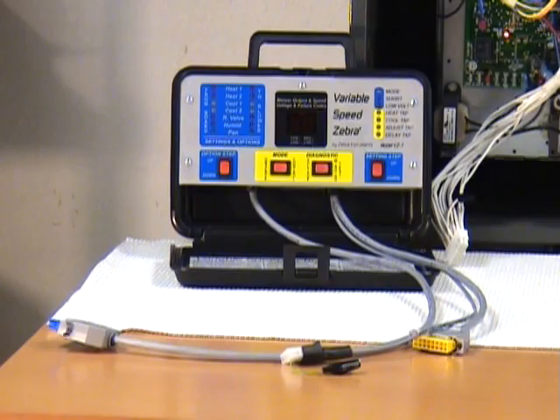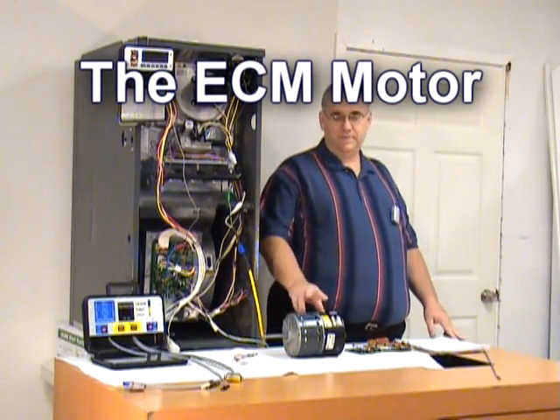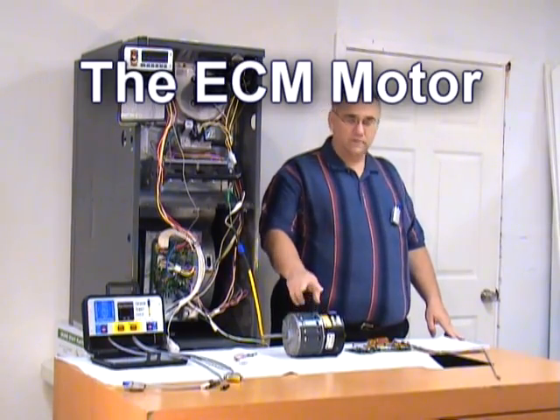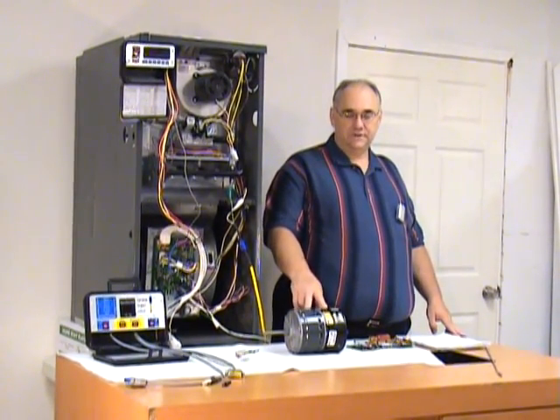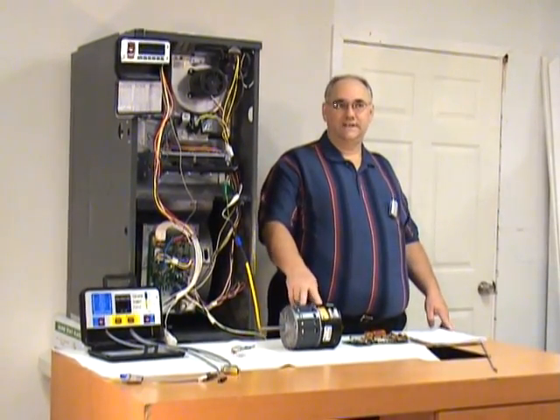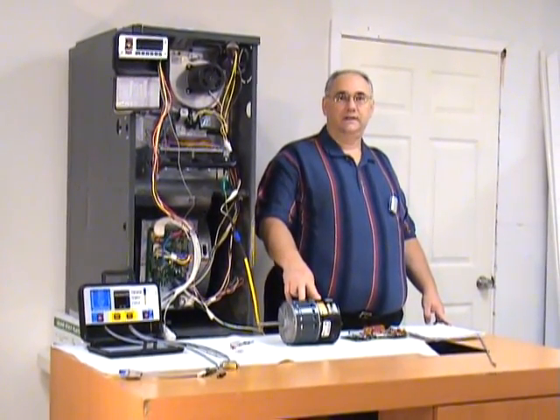It might damage it. In early 2007, the variable speed motor in one form or another was installed in over 12 million units. The efficiency rules mandated by the U.S. government in early 2006 are drastically increasing the installed base of ECM motors. Many service techs are seeing these motors when they're responding to service calls for the furnaces that they're installed in. Many techs are seeing them for the first time. I remember the first time that I ever saw one, I says, where are the common, high, medium, and low wires that I'm normally used to, and why are there 21 wires going to these things, and what do they do? The earliest units were made in 1992, so we're starting to see some breakdowns come through on those older units.